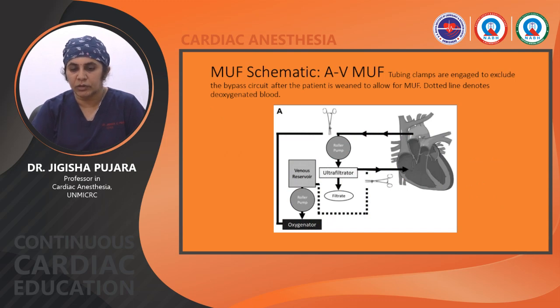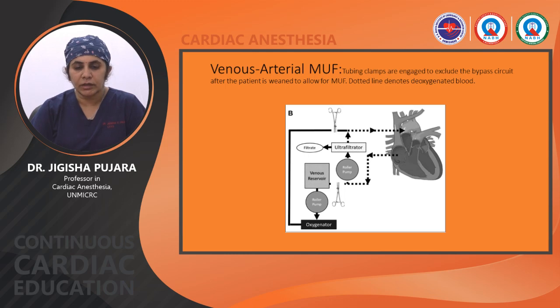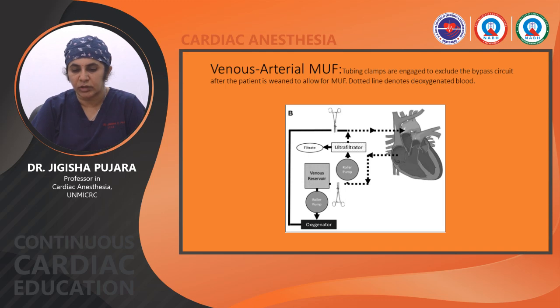In both AV and VA MUF systems, isolated from the CPB circuit, blood volume can be independently transfused from the CPB circuit to maintain satisfactory hemodynamics after weaning. In AV-MUF, the tubing clamp is engaged to exclude the bypass circuit after the patient is weaned; from the cardioplegia cannula, blood passes through the roller pump, ultrafiltration, and then back to the venous side. In VA-MUF, two clamps exclude the circuit; venous blood goes to the roller pump, then to the ultrafiltrator, with the retained volume returning to the aorta via the CPB line.